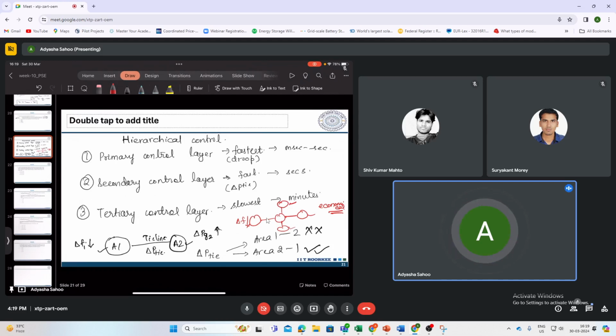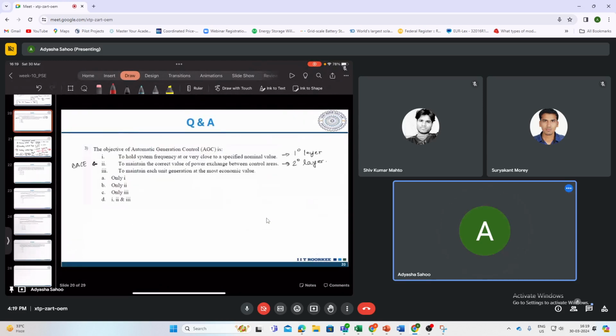That will be decided using this tertiary control layer, or what we call AGC. Its aim is to determine the most economical action to be taken to correct the frequency. This is your tertiary layer, the AGC, to maintain each unit of generation at the most economic value. So from here, I can say that only this three is the objective of AGC.